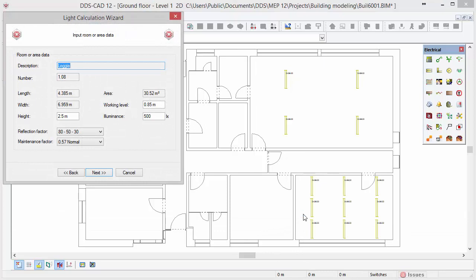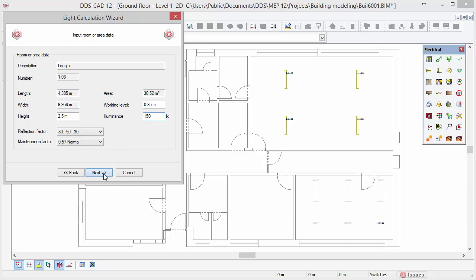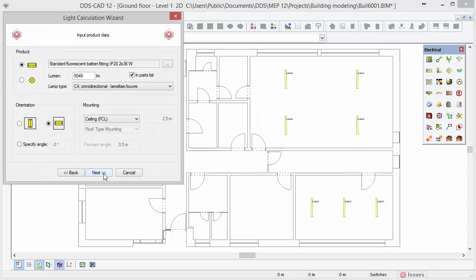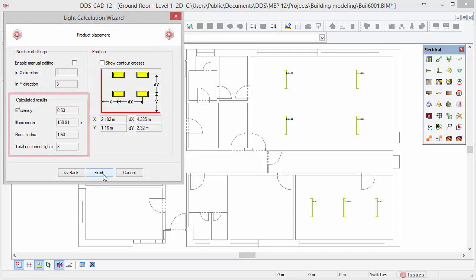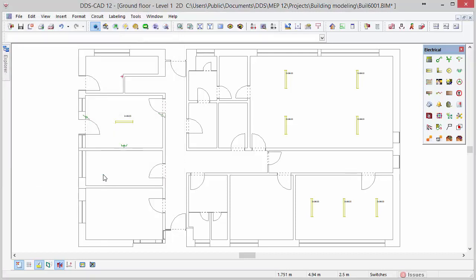The calculation dialog opens. Here you can define parameters such as the mounting height, working level and illuminance. Let's change the illuminance to 150 lux and press next. Default values are applied to the lamp type, orientation and mounting type. If required you can edit these settings and press next to continue. Finally we see the lamp placement which you can also edit. Press finish to complete the light calculation for this room and press escape to close the function.